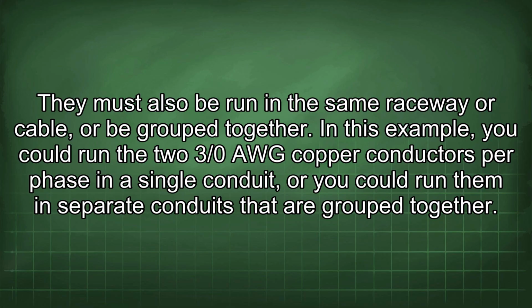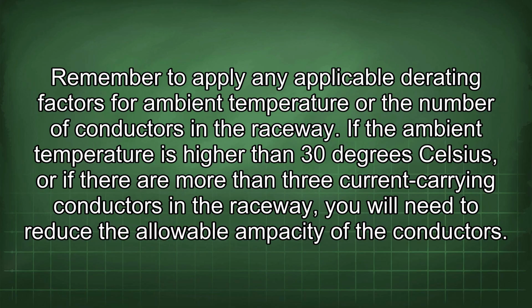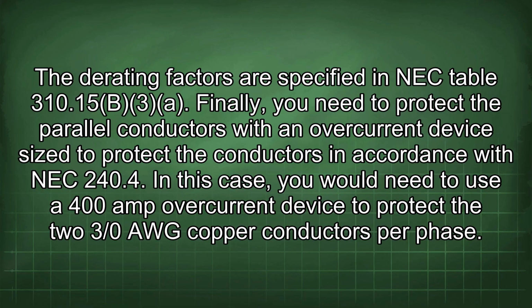In this example, you could run the 2 3/0 AWG copper conductors per phase in a single conduit, or you could run them in separate conduits that are grouped together. Remember to apply any applicable derating factors for ambient temperature or the number of conductors in the raceway. If the ambient temperature is higher than 30 degrees Celsius, or if there are more than 3 current-carrying conductors in the raceway, you will need to reduce the allowable ampacity of the conductors. The derating factors are specified in NEC Table 310.15(B)(3).